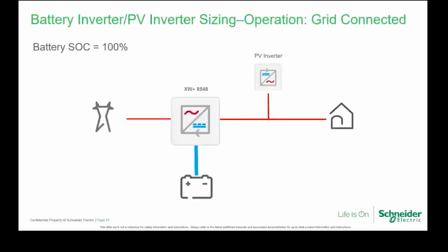So I'm looking at some of the energy flows on the grid-tied inverter AC couple. When we have the battery at, say, 100%, we can have a load of, say, 5,000 watts, with 2,000 watts coming from the PV inverter. Then what's going to happen? We still need to supply the power for the loads. If you enable grid support on the XW, it means that you're going to have 3,000 watts coming from the battery bank, okay? Because you enabled grid support, and nothing from the grid itself.